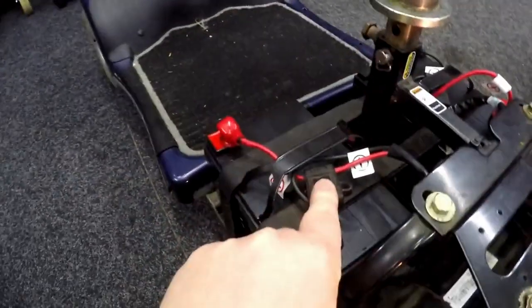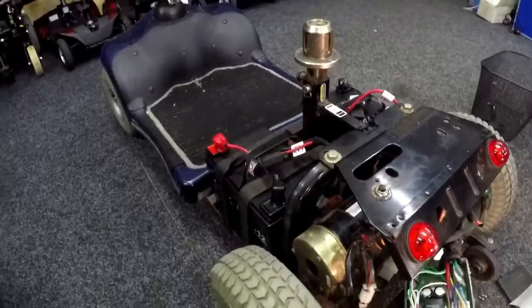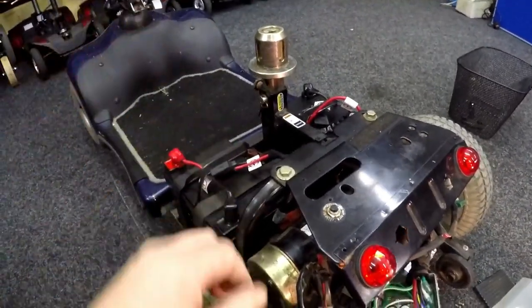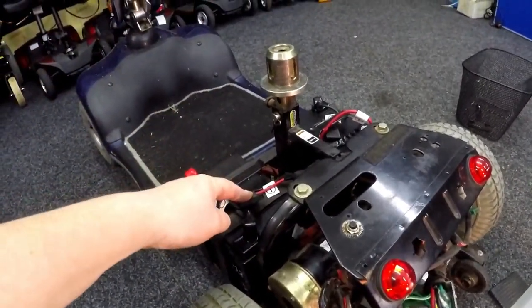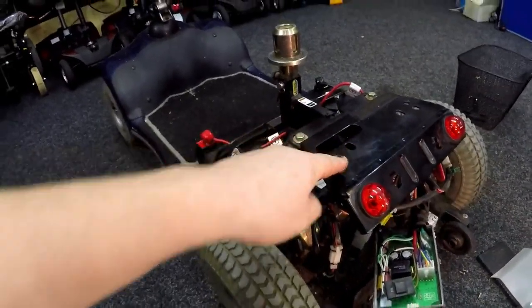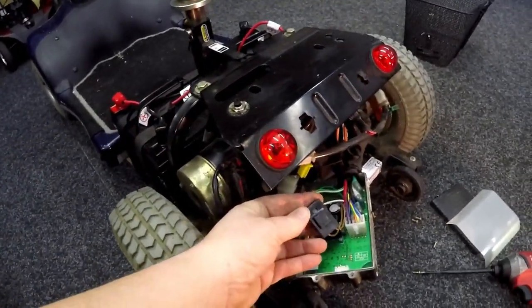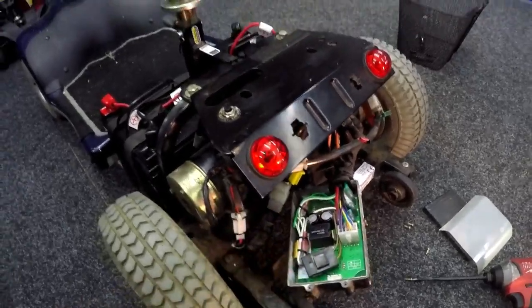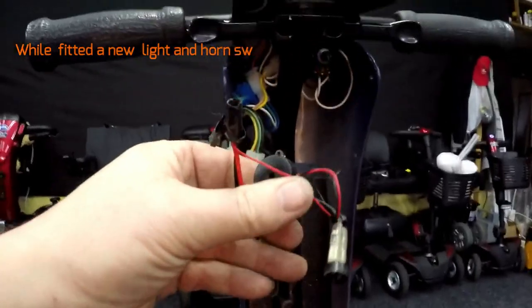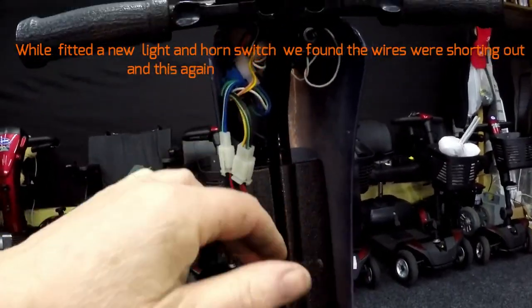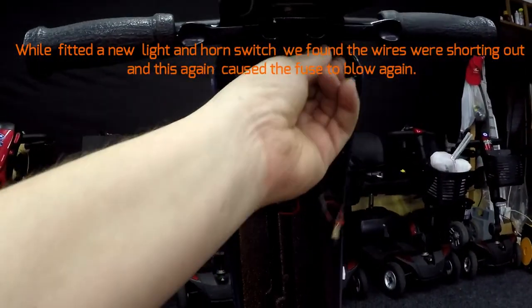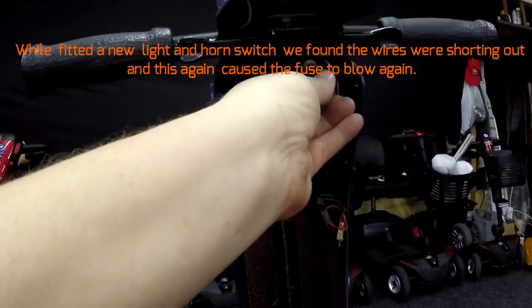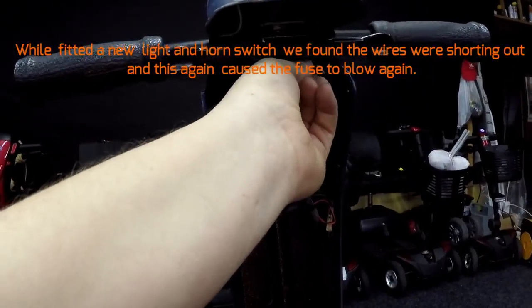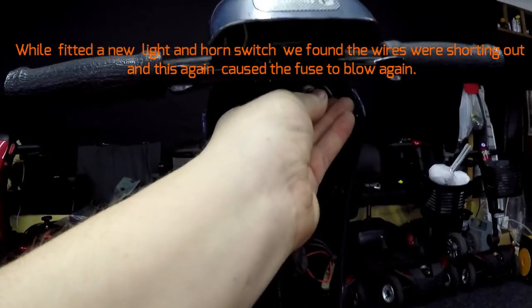See, the fuses could have gone in here as well, but they didn't because we had the 24 volts at the charging point. If one of them went, you would have got 0 voltage, then you would have gone to your fuses here or your circuit breaker. And that's just your power. And that's it, sorted. Easy repair. I'm going to speak to the customer to see if he's wanting these sorted or not. There you can see an extra speed put in here. So you can actually make it even slower, but you won't be able to make it any faster.